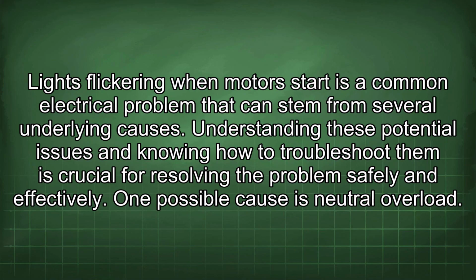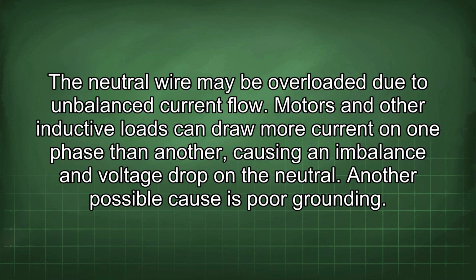Lights flickering when motors start is a common electrical problem that can stem from several underlying causes. Understanding these potential issues and knowing how to troubleshoot them is crucial for resolving the problem safely and effectively. One possible cause is neutral overload. The neutral wire may be overloaded due to unbalanced current flow.